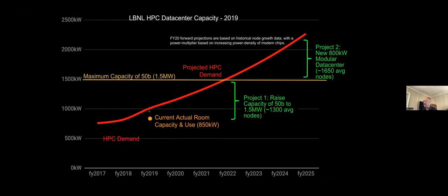Now, a thing about our data center is that we knew this was coming, and so we had embarked on what you see here called Project One, to upgrade the capacity of the room to 1.5 megawatts. This was actually a very clever re-engineering of our data center to get more capacity out of it.